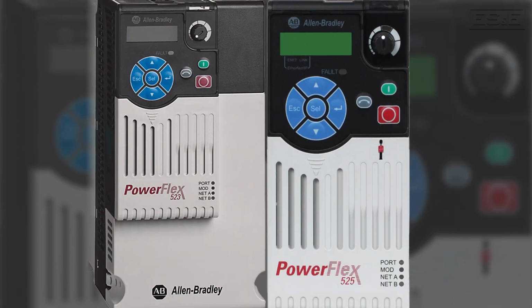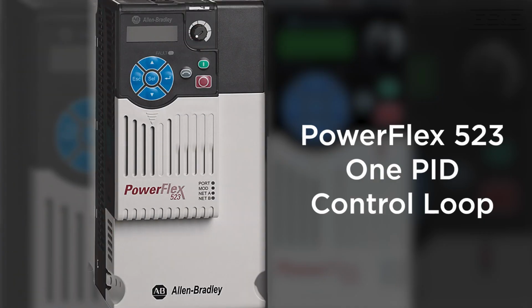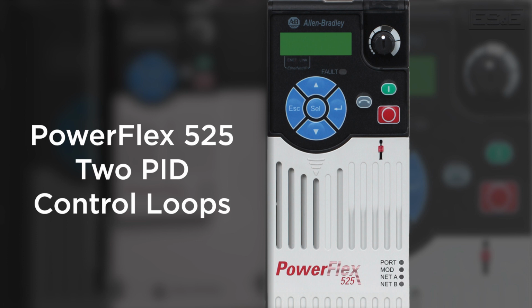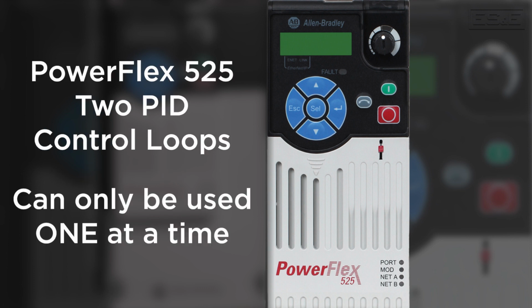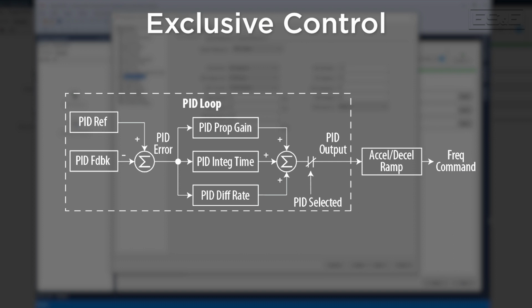It's important to note that the PowerFlex 523 has one PID control loop, while the PowerFlex 525 has two PID control loops. However, with the 525, they can only be used one at a time. Two basic configuration examples where the PID loop may be used are exclusive control and trim control. In exclusive control, the speed reference becomes zero, and the PID output becomes the entire frequency command.